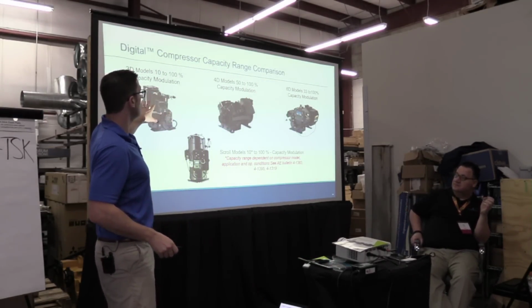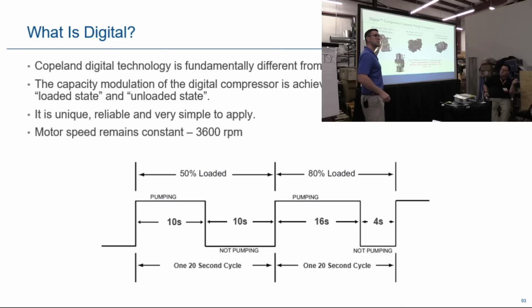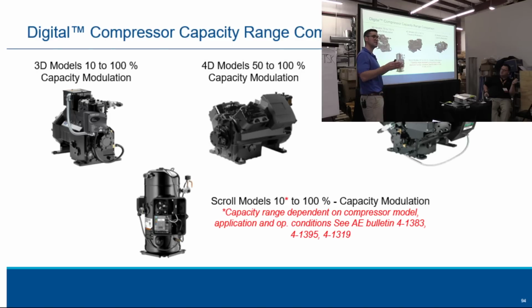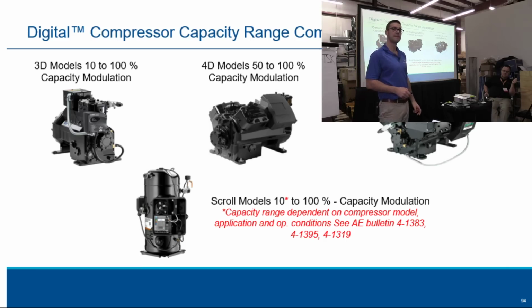So our 3D models can go from 10% to 100% capacity. So with a 100,000 BTU compressor, that's 10,000 to 100,000 BTUs. We've got our 4D models, 50 to 100, and 6D, 33 to 100. So you'll have a block suction, you'll have a digital, and you'll have a fixed head. And then scrolls, some of them can go down to 10% to 100%. The hermetics was the one I was talking about.